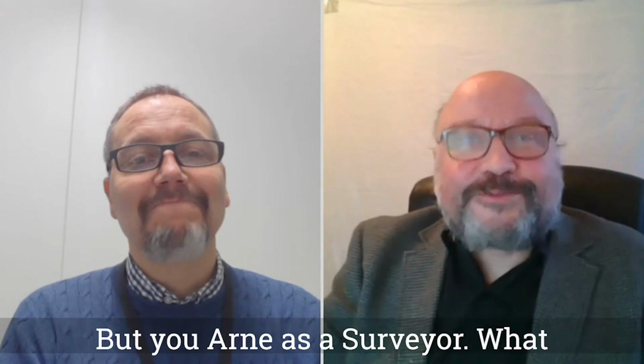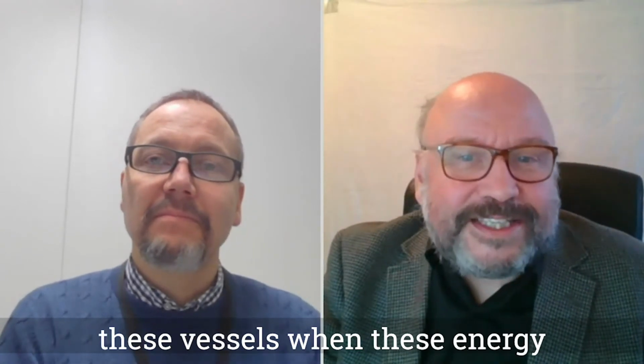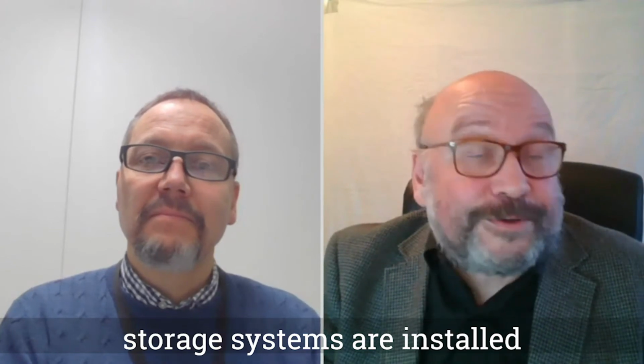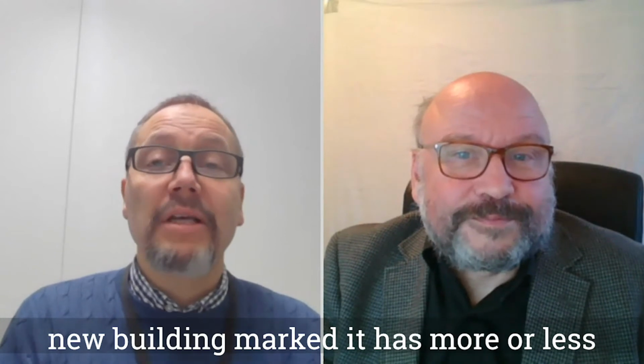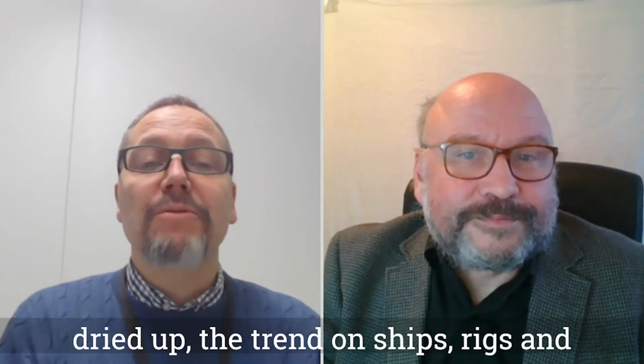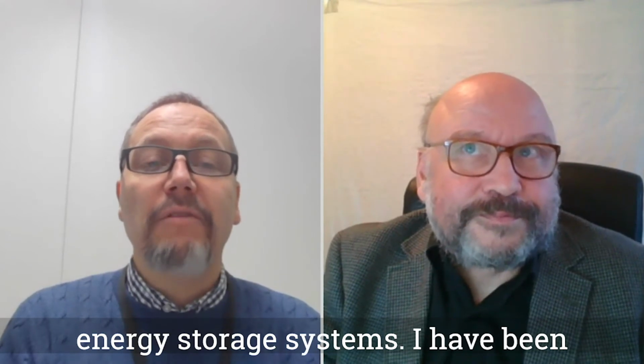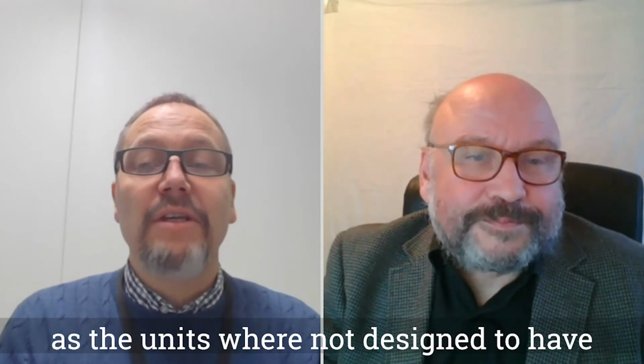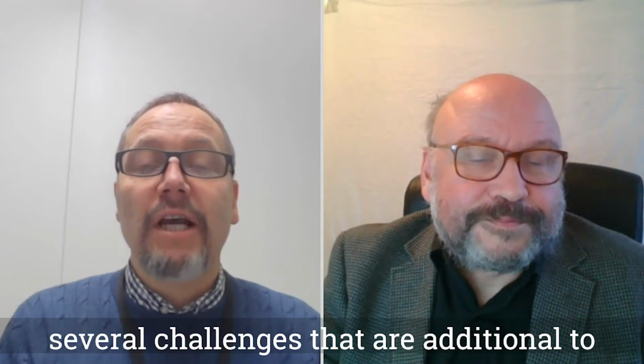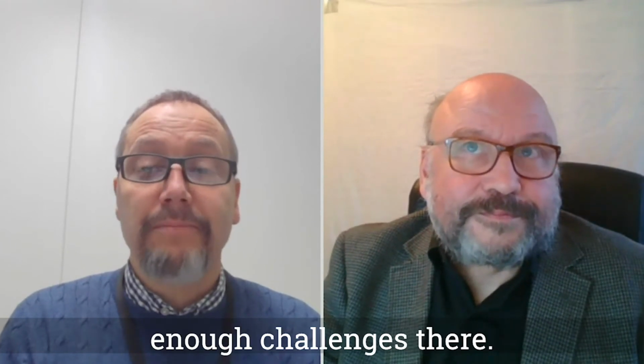But you, Arne, as a surveyor, what challenges do you see? You are on board this vessel when this energy storage system is installed. Well, Sverre, as you know, the offshore new building market has more or less dried up. The trend on ships, rigs, and offshore installations is to retrofit electrical energy storage systems. And I've been involved in several retrofit projects. As the units were not designed to have the energy storage systems on board, there are several challenges that are additional to the challenges found with the normal installation of an energy storage system in a new building yard, and there are enough challenges there.